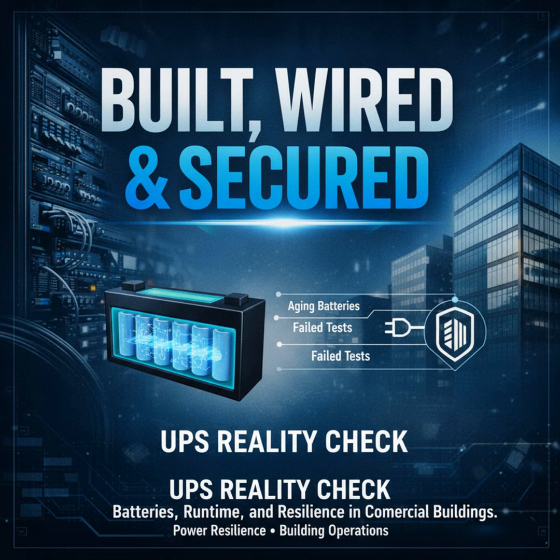Segment 1. Causes. Michael, walk us through the common failure modes you see in the field. 3 big buckets. First, battery aging. Batteries lose capacity over years, sometimes dramatically faster than paperwork suggests. A unit rated for 10 years effectively behaves like a shorter duration battery after 4 to 6 years if maintenance or environmental conditions are poor.